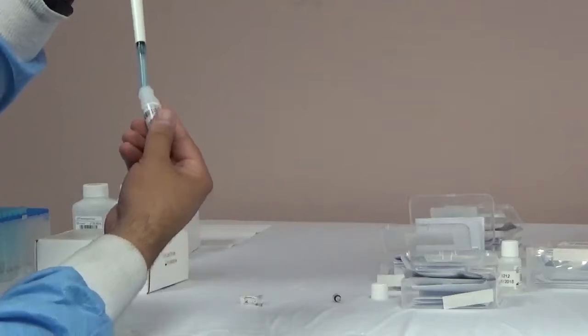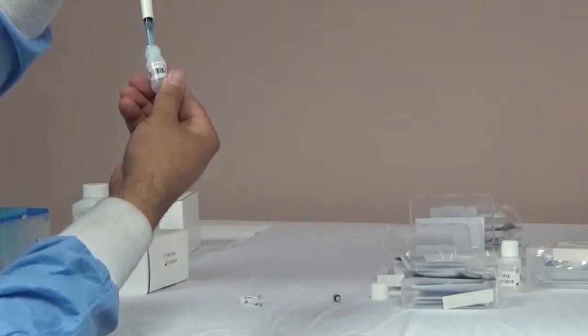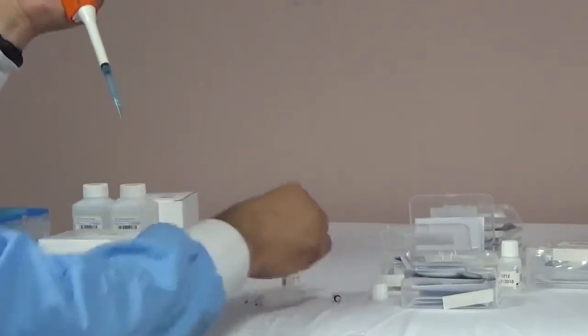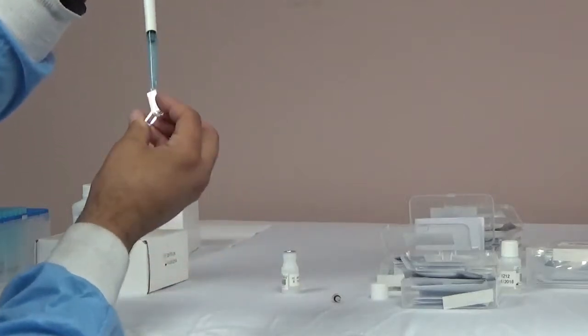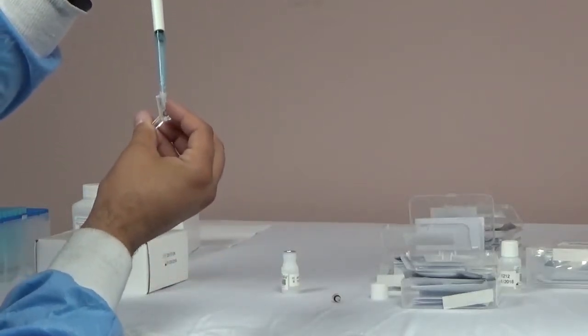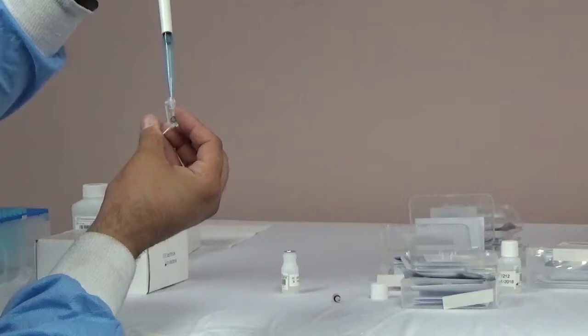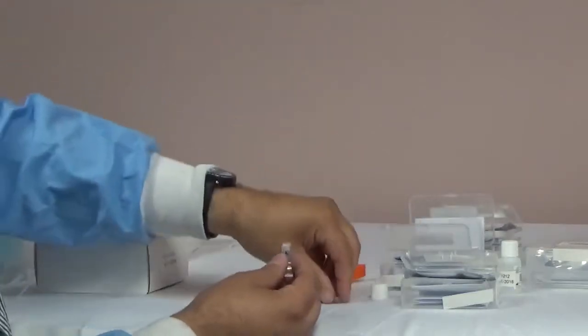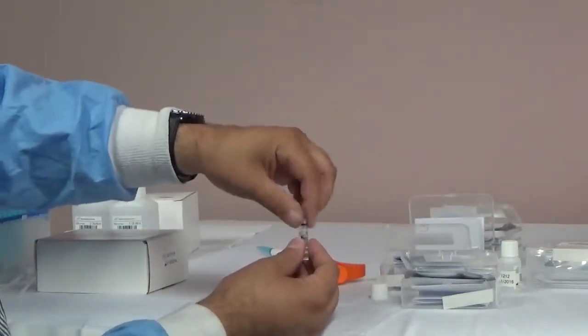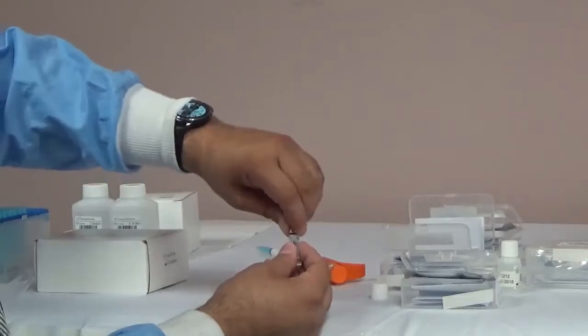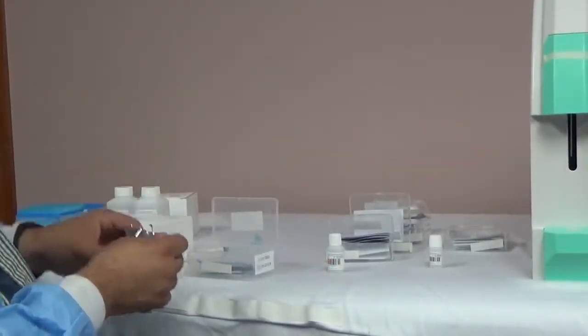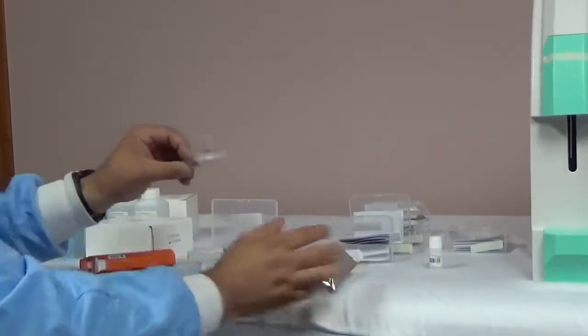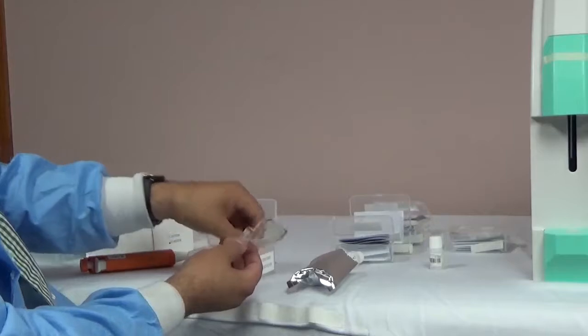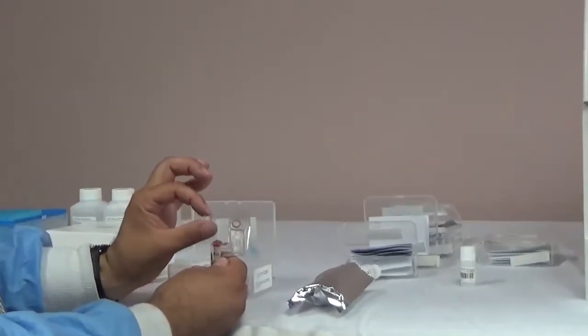The fill line should be about halfway between the letters. Replace the cap of the electrode by hand, do not use any tools. After you have replaced the cap, hold the electrode from the top and flick the bottom to remove any air bubbles. Make sure that when you fill the electrodes, you use the correct solution: ISE refill solution for the ISE electrodes and reference refill solution for the reference electrode. Also use a different pipette if you switch between the two types of solutions.